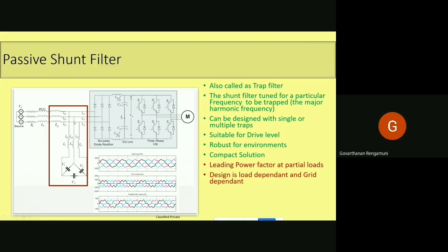Here I have shown only one section, only one notch filter, which can be designed for eliminating the fifth harmonic. If you want to eliminate, for example, the 11th harmonic, you need to add one more notch filter tuned for the 11th harmonic. So this is a simple approach for eliminating harmonics. You can see the waveforms here.